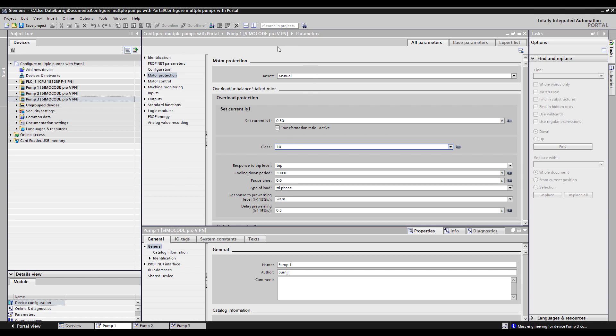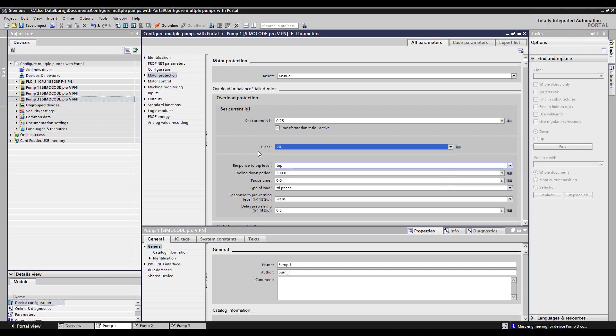Here I'm looking at the pump one parameters and you'll see the set current is currently at 0.3 amps. Let's change that to 0.75 amps and the trip class, let's extend that to a Class 20 because of the application.